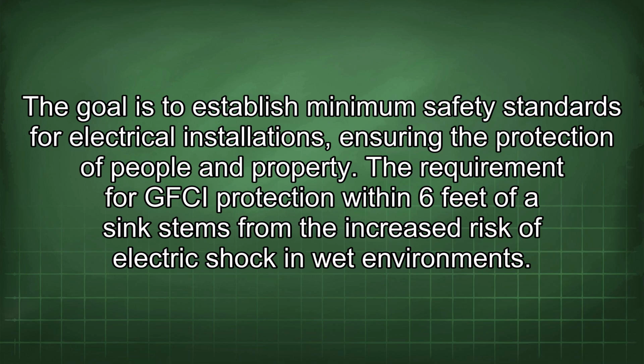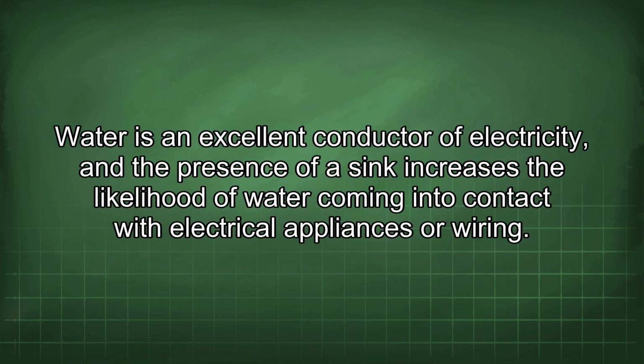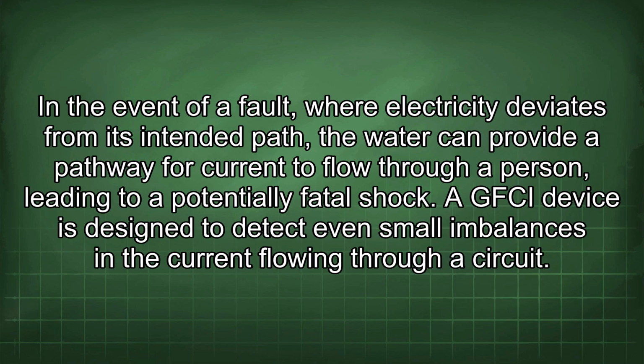The requirement for GFCI protection within 6 feet of a sink stems from the increased risk of electric shock in wet environments. Water is an excellent conductor of electricity, and the presence of a sink increases the likelihood of water coming into contact with electrical appliances or wiring. In the event of a fault, where electricity deviates from its intended path, the water can provide a pathway for current to flow through a person, leading to a potentially fatal shock.